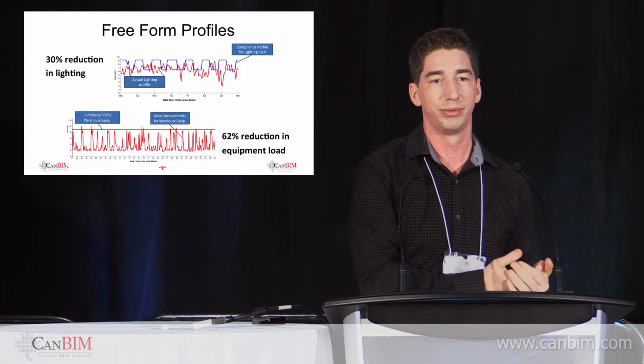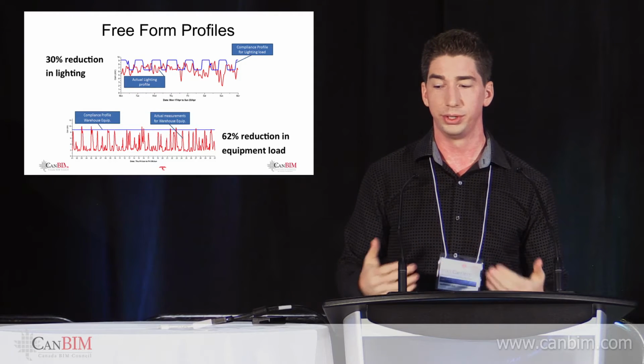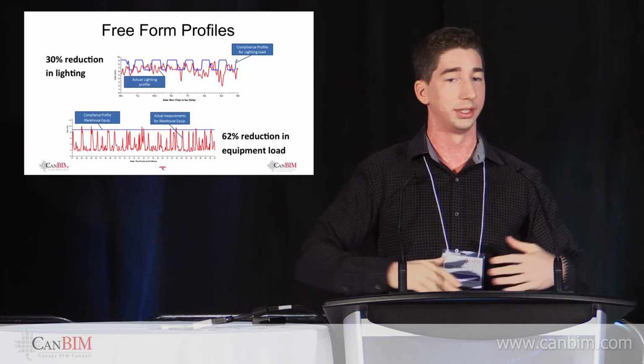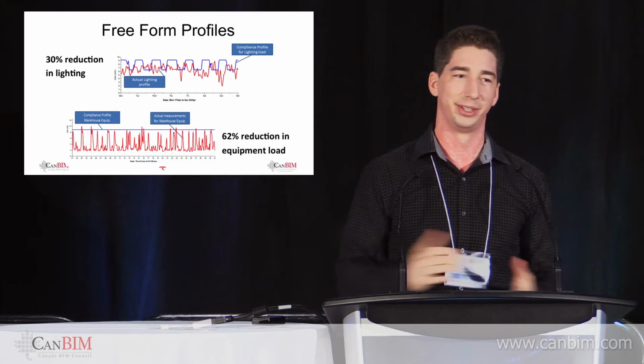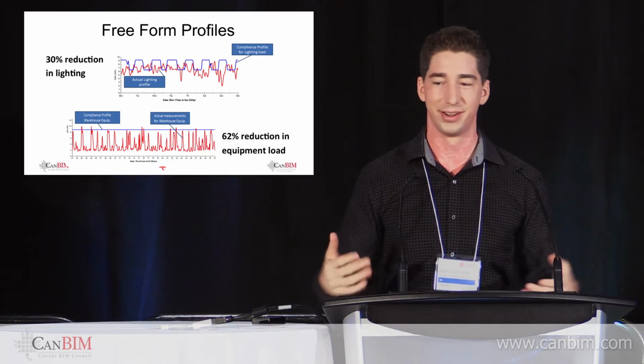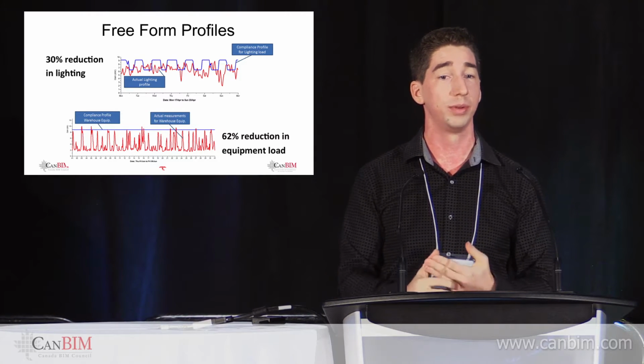And what we've estimated is we've reduced our lighting load by 30%. We've also reduced our equipment load. The equipment is basically assumed to be using this much energy all the time, which is not really the case. Your computers go on and off. So we have a 62% load reduction in equipment.